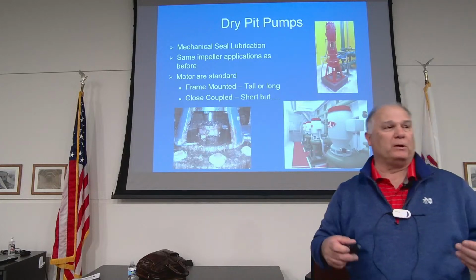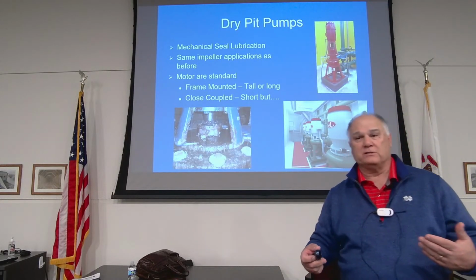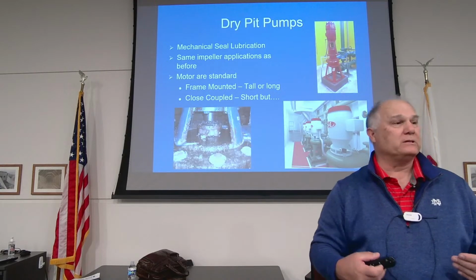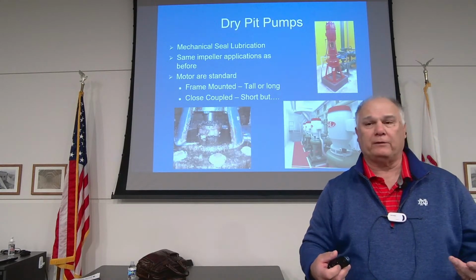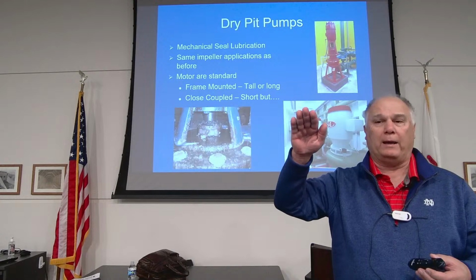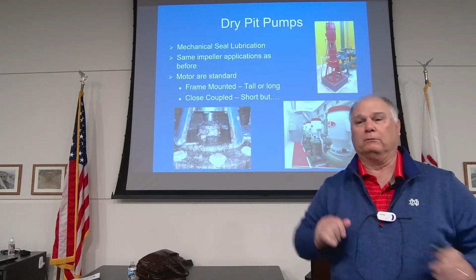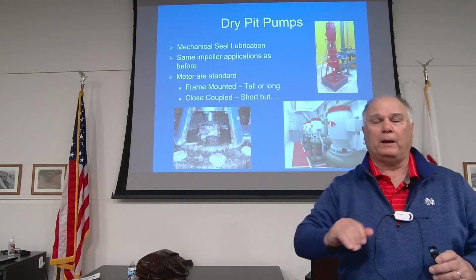So if you have a pump that plugs up on a regular basis, see how many GPM you're pumping, and see what the riser pipe velocity is and your check valve velocity, because that thing needs to open up the whole way to flush all that crap through. Because if it doesn't open up the whole way, it's going to plug.